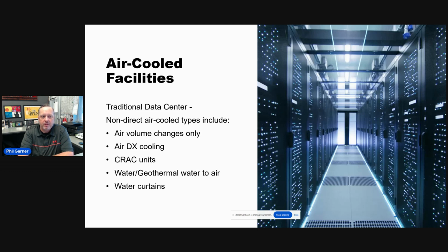The main piece of air cooled that we see a lot in the Bitcoin mining world is just air volume changes. So all that is bringing whatever the air temperature is outside into your facility, running it through your miners out of the hot aisle, either up and out or across and out, to create what's called the delta T. The delta T is the difference between the temperature outside and the temperature inside. So let's say you have 80 degrees outside and 105 degrees in your hot aisle, and you bring that 80 in with a 15-degree delta, you're going to be able to keep that air around 95 degrees instead of 105 because of that 80 degrees outside.